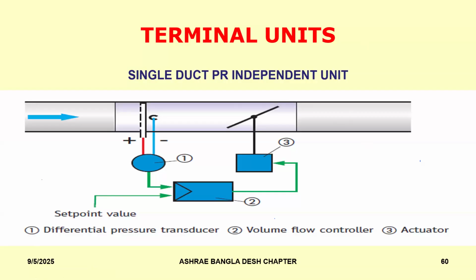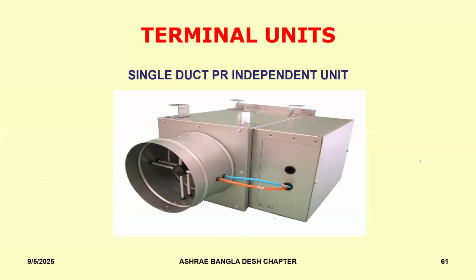Now, apart from keeping the people comfortable and providing good air quality, by varying the actual amount of air going through based on demand, you are able to modulate the speed of the fan. And all of you are familiar with the fan law, which says that the power consumed varies as the cube of the speed. So if I am able to reduce the airflow when it is not required, reducing the airflow means reducing the speed of the fan. I'm also able to save a lot of energy. Therefore, this device not just helps you to meet your energy conservation requirements, it also helps you to optimize your air quality and thermal comfort within the space.